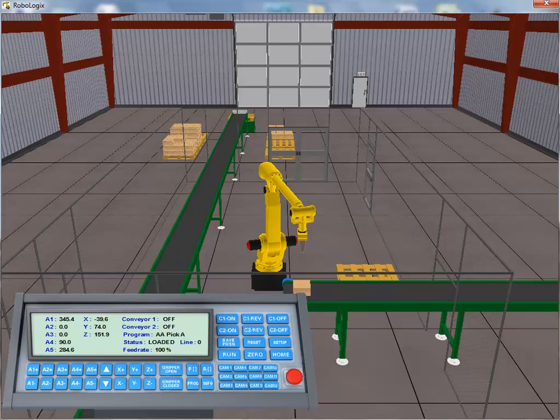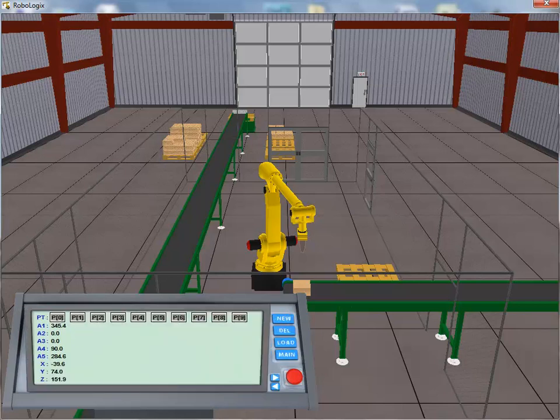With our first target position acquired, we click on the Save Position button to store this location to the position register. To confirm the acquisition of the target location, we click on the Position Register button to bring up the position register window. As can be seen, the target information location has been stored to the position register under the P0 index number.